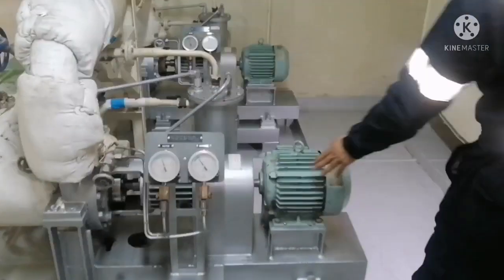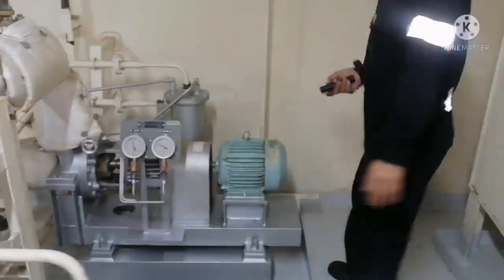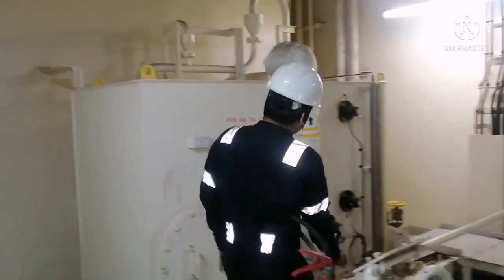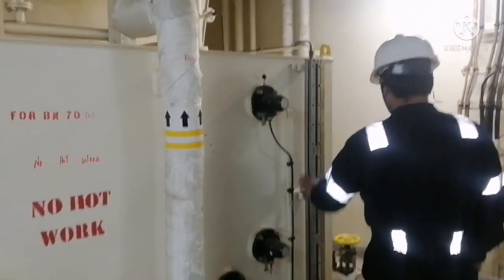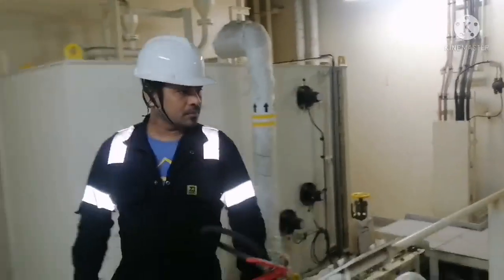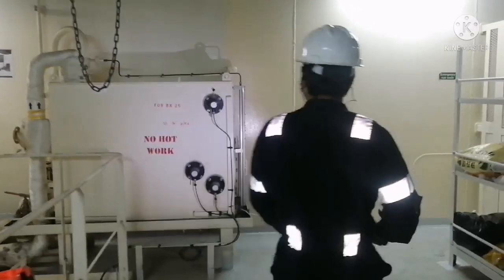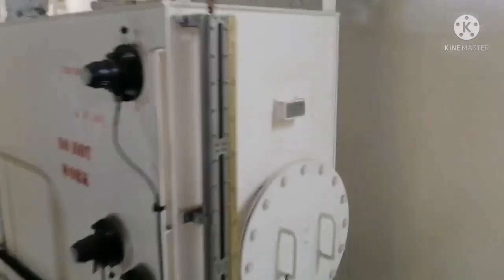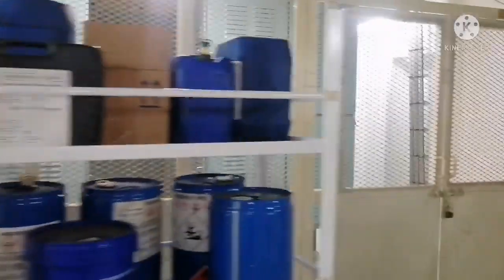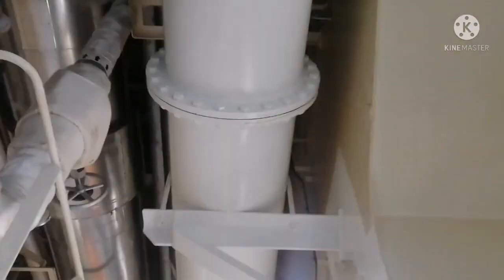And this is your boiler water circulating pump. Just look that the pressures are okay, and just check for any abnormality in the motors. Just keep a hand on the motor and see whether it's overheated or something. If it is overheated, then there may be a problem. And just check the level for the cylinder oil, and ensure before putting UMS, you have to fill the cylinder oil tank whichever is in use. And that is a very important thing that we need to check. And check that the chemicals are secured properly, and check if there is any abnormality on the platform. And here I can find some leakages, some small, minor leakage. I'll rectify it. Okay, so this platform is done.